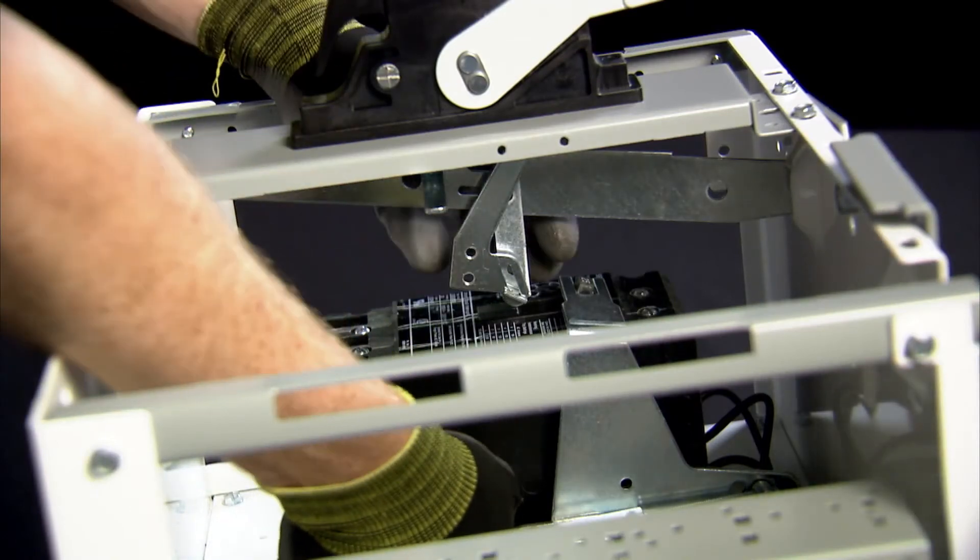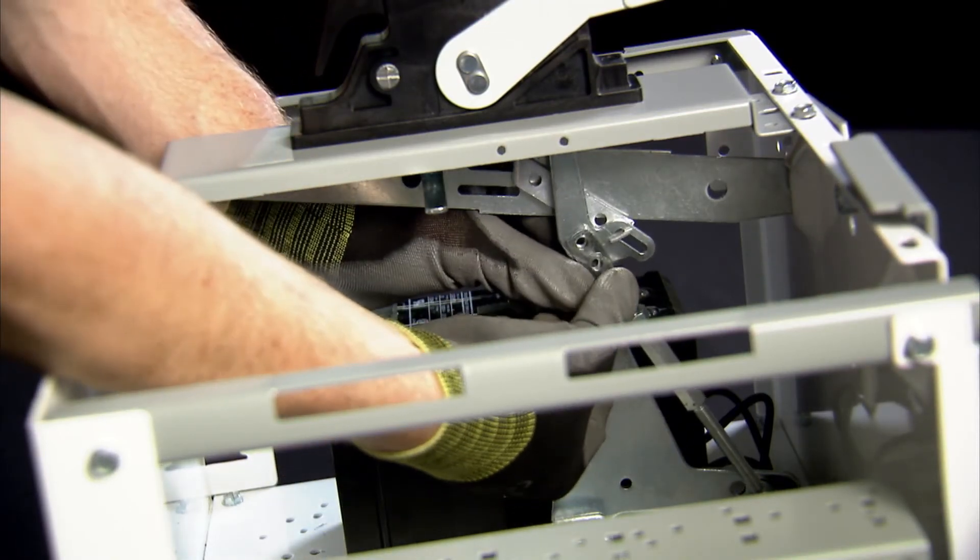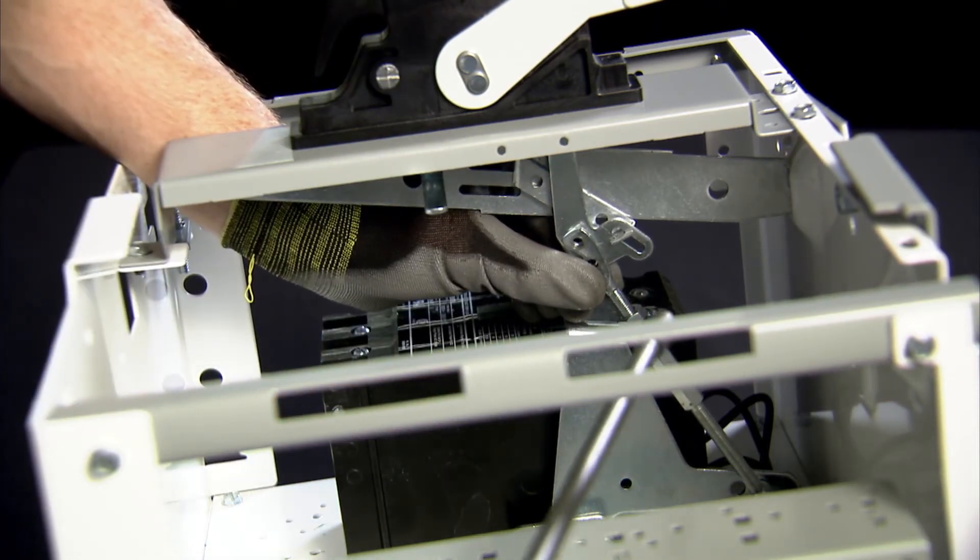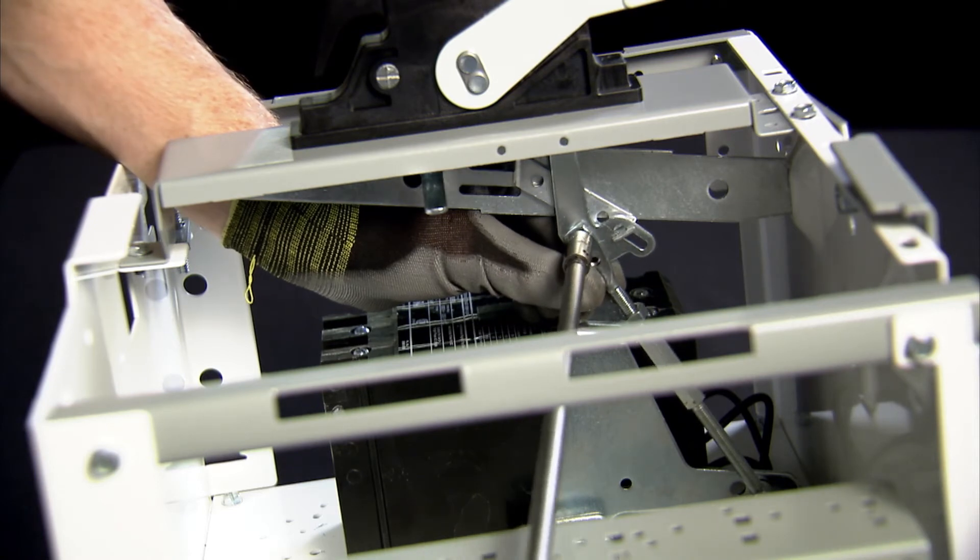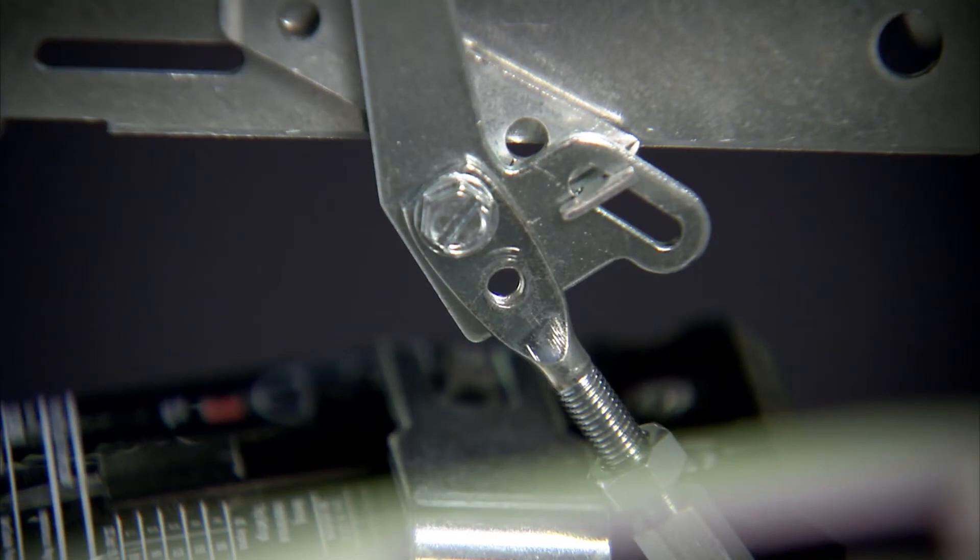The handle linkage assembly must then be attached to the breaker operator. The length of the rod attached to the breaker operator may need to be adjusted to align the screw holes. Twist the turnbuckle to adjust the length and then fasten the arm to the linkage with the provided screws.